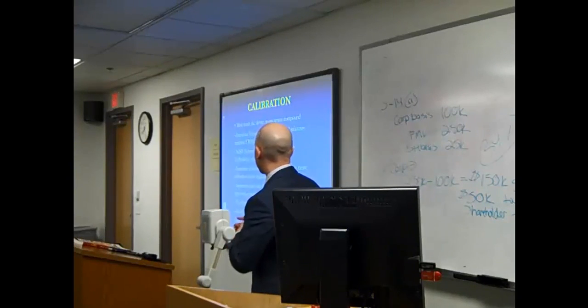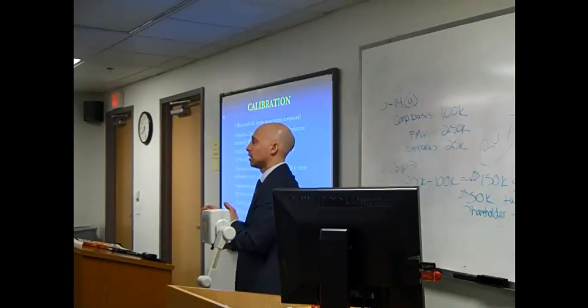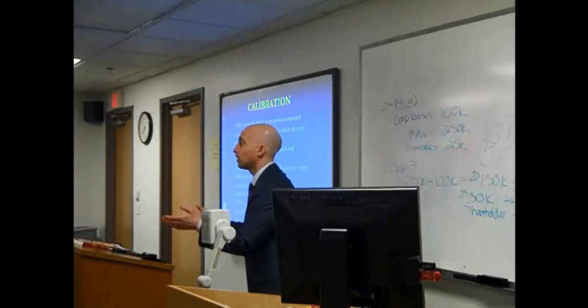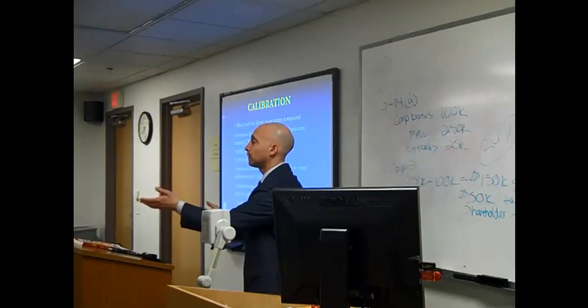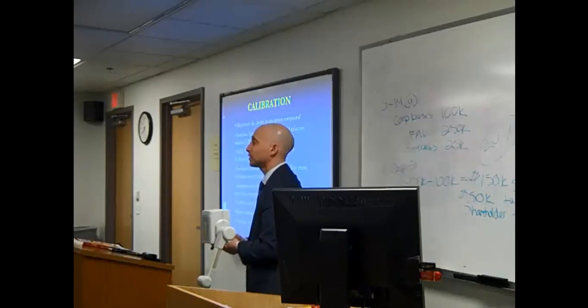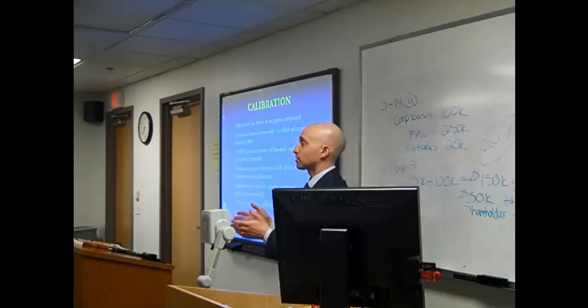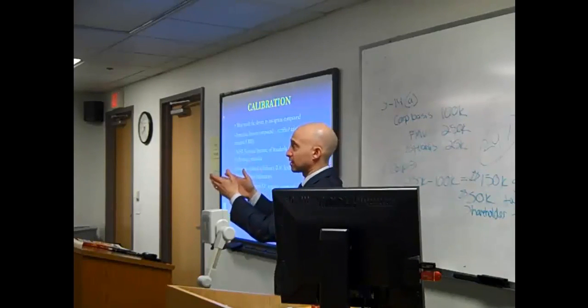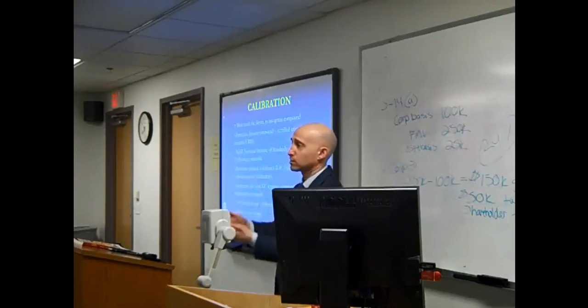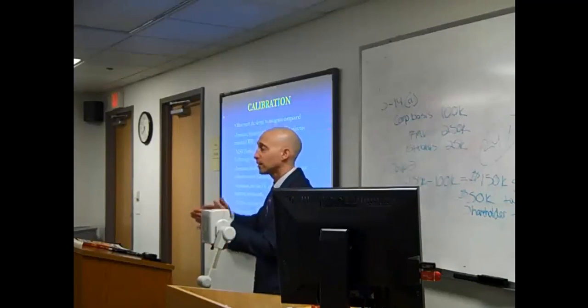And then you want to create what's called a calibration curve. So, all right, how do we know what's 0.01 and what's 0.15? Well, you got to teach the machine how much ethanol, what it looks like essentially to have a 0.15 BAC, what it looks like to have a 0.05 BAC, and create a curve.